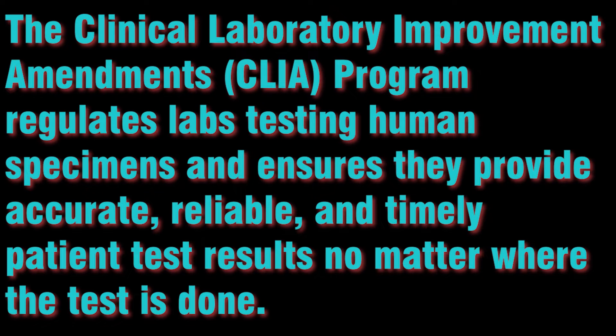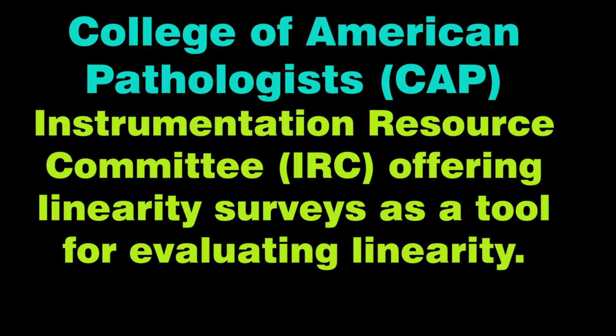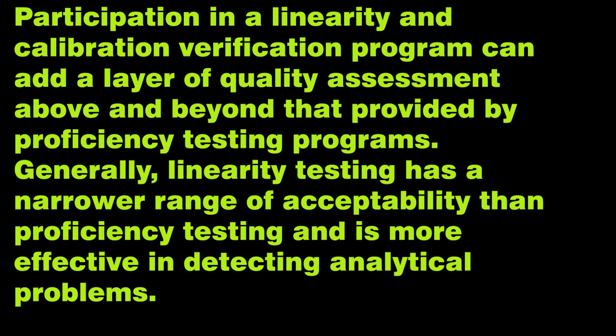Standard institute CLSI, as per the EP06-A guideline, defines linearity as the ability within a given range to provide results that are directly proportional to the concentration of the component in the test sample. In simple terms, we are checking the linear calibration curve at the low and higher levels and also the middle range with known concentration samples.